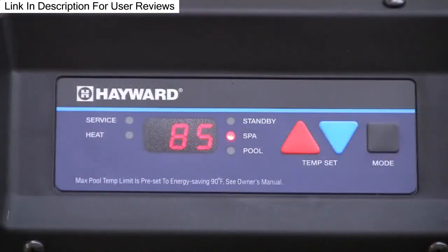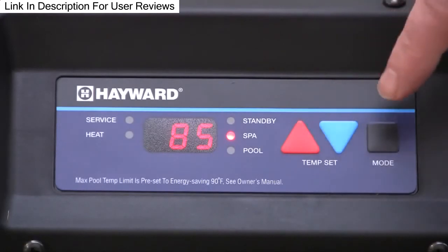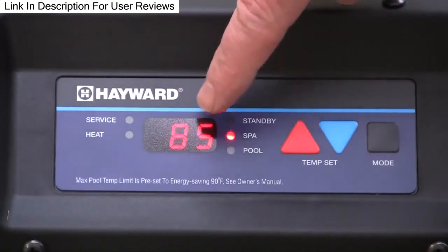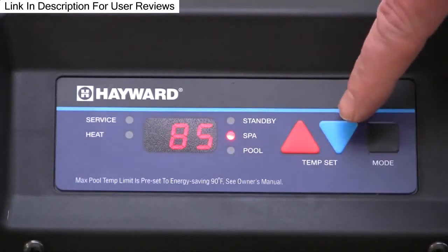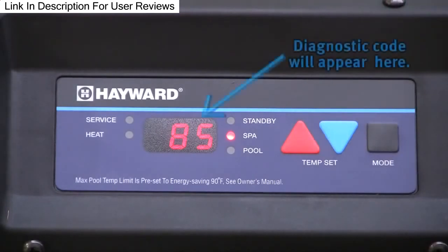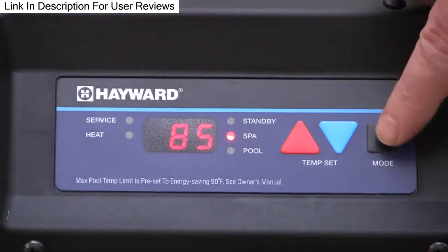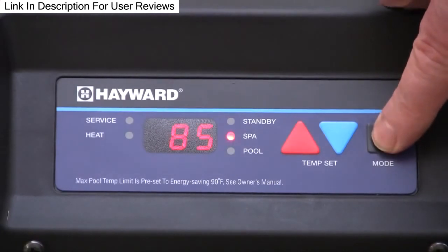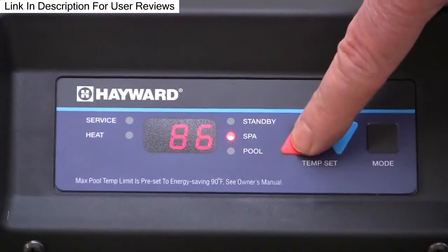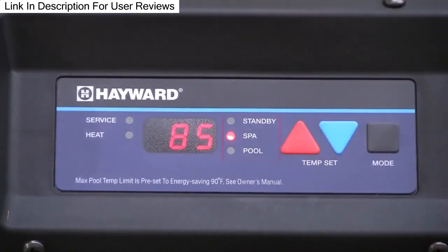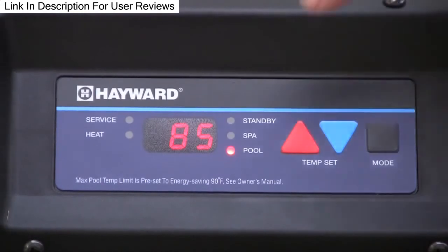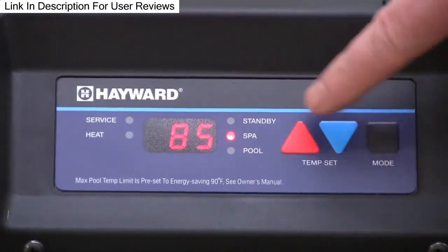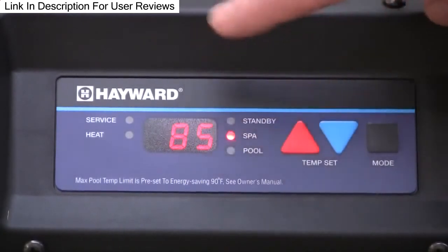The heater is equipped with a temperature control for controlling the pool and spa water temperatures. Individual pool and spa set points can be entered using the keypad. The control displays the pool or spa water temperature. If a problem were to occur, a diagnostic code will be displayed to help direct a technician in solving the problem. The mode button is used to set the heater for pool or spa operation. Once set to either pool or spa, use the up and down arrows to adjust the set point to the desired temperatures. There are 3 modes for heater operation which must be manually set. Pool. The heater will operate as needed to warm the pool to the set temperature. Spa. The heater will operate as needed to warm the spa to the set temperature. Standby. The heater will not operate in standby mode.